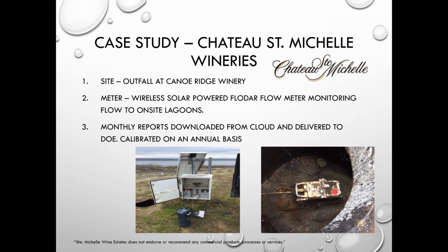This sensor is actually sitting over the top of an open cut pipe. So they basically took the data and reported it over to DOE, I think on a monthly report, and they're able to capture their reports online and give it to the DOE. And then they ask us to come in once a year and calibrate the flow meter with our portable FH950 and ultrasonic.